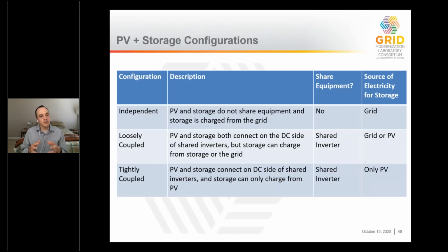If you had a solar and storage system you wanted to combine, there are different configuration options to evaluate. We start by having these completely independent—a PV plant and a storage plant sharing no equipment or infrastructure, so there's no point of interconnection limit constraining output, and the storage can charge and discharge from the grid as needed. That's our baseline configuration.